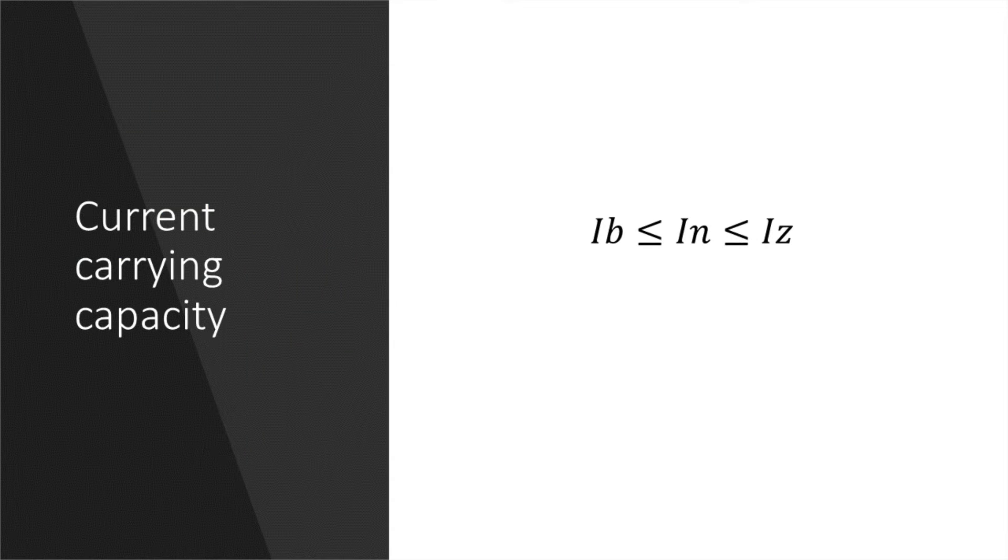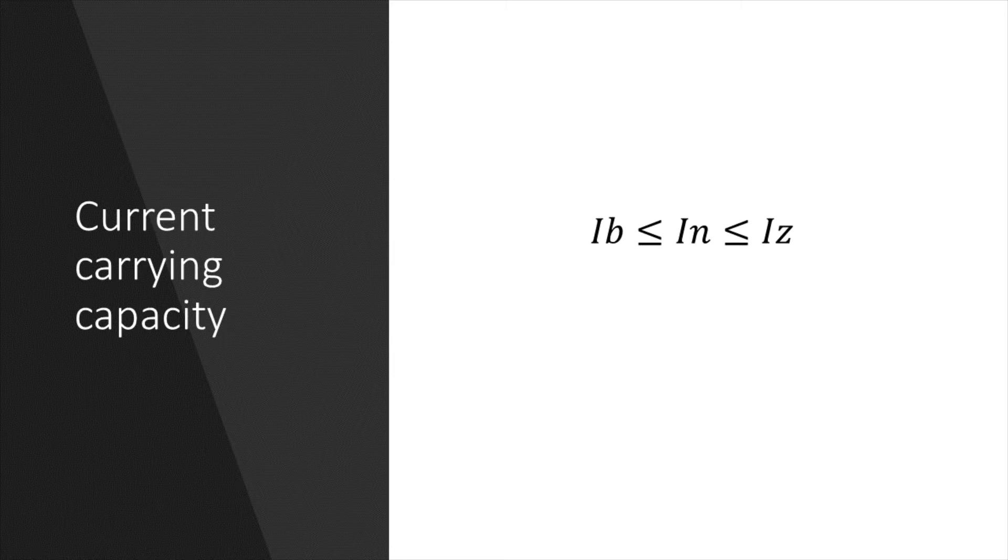To calculate the current carrying capacity, we need to know the design current IB, then select the size of the protective device IN, and then select the as-installed current carrying capacity of the cable IZ.